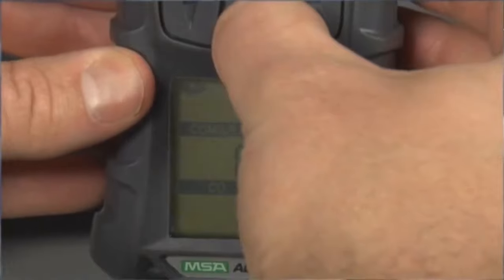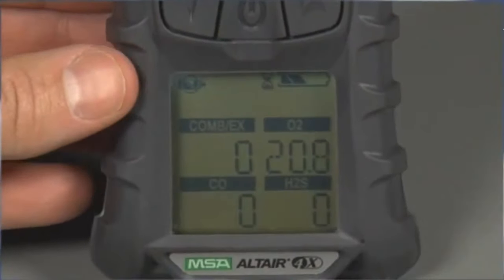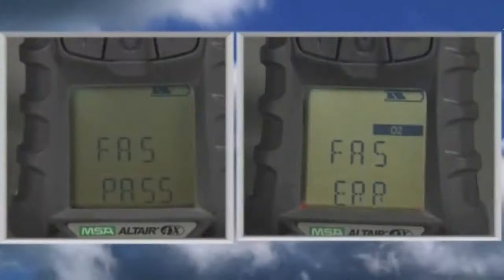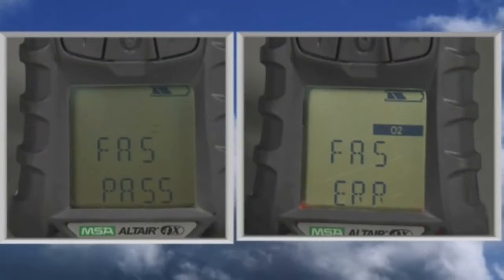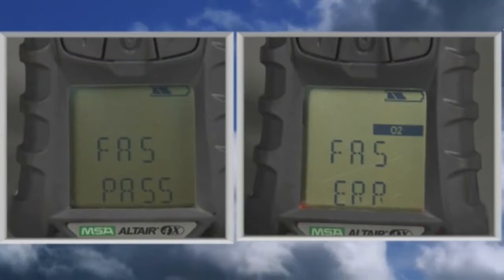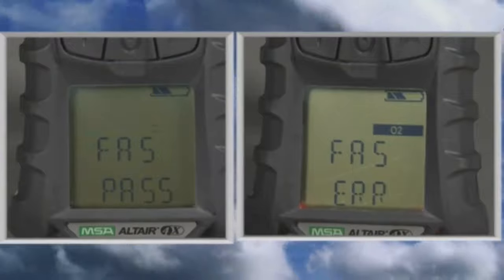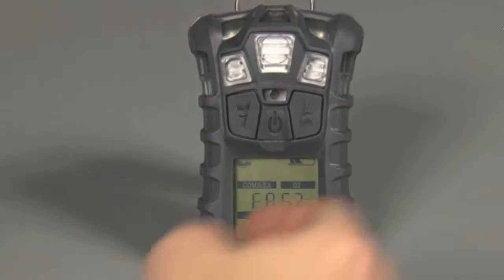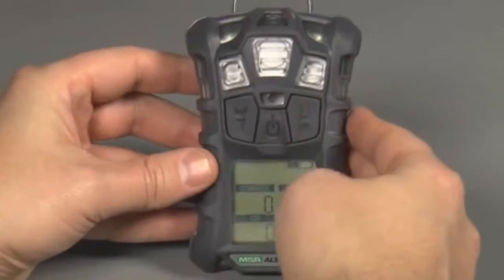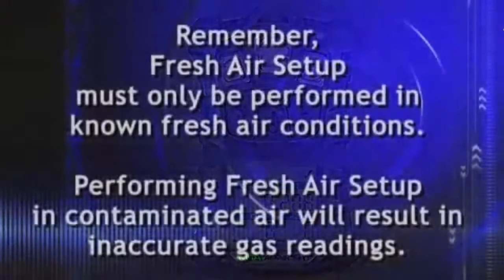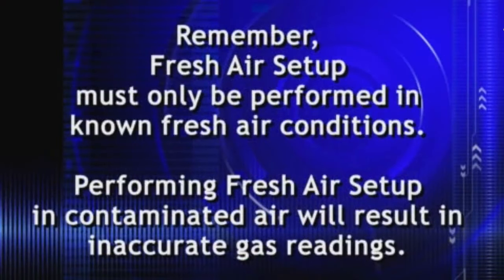To run fresh air setup at this time, simply push the center or Accept button. FAS Pass or FAS Error will quickly display. If FAS Error displays, a full instrument calibration should be performed. To skip fresh air setup, push the Page Up button or simply wait 10 seconds. Remember, fresh air setup must only be performed in known fresh air conditions. Performing fresh air setup in contaminated air will result in inaccurate gas readings.